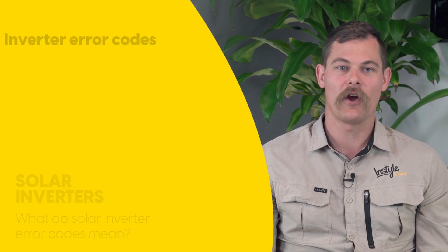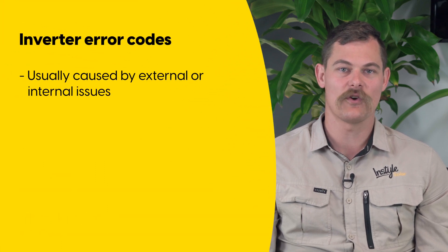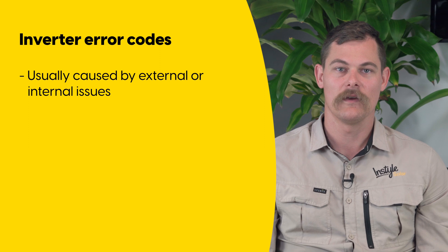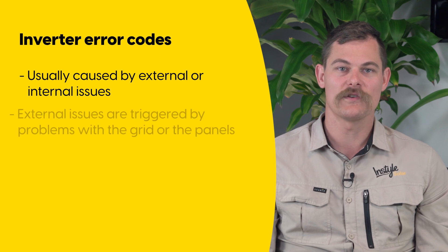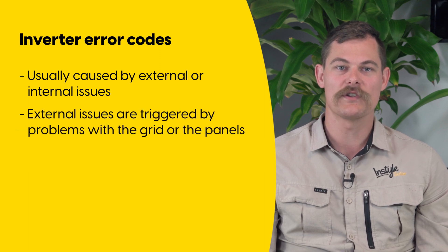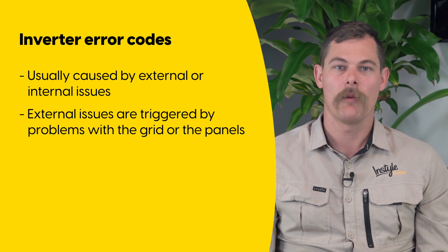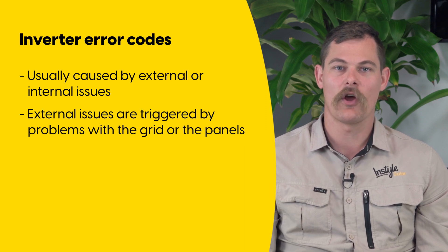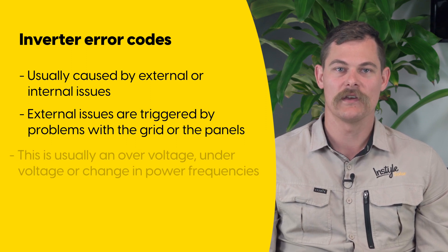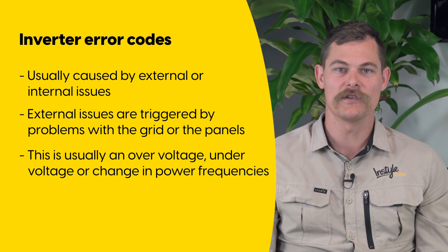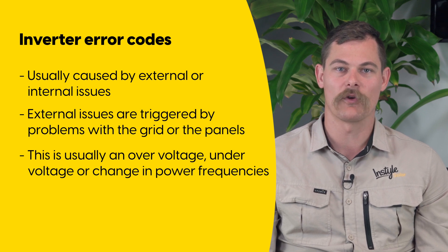Inverter error codes are usually caused by either external or internal issues. External issues are triggered by electrical issues that originate either from the grid or from the solar panels. Most of the time this is due to either an over voltage, under voltage, or a change in the frequency of the power that is coming from the grid or from the panels.